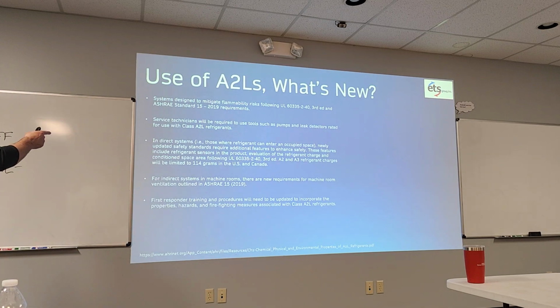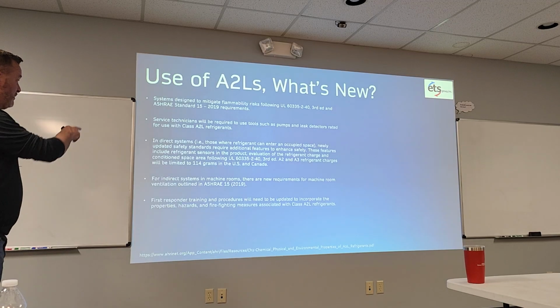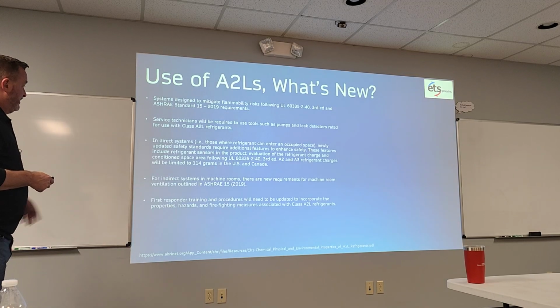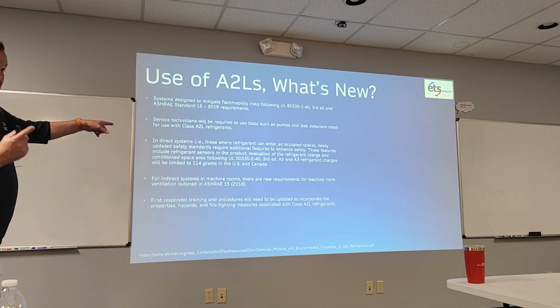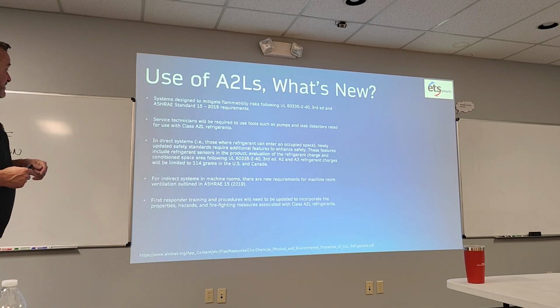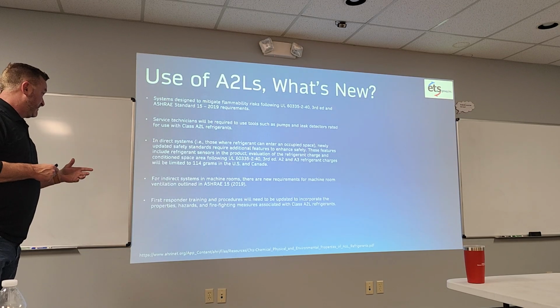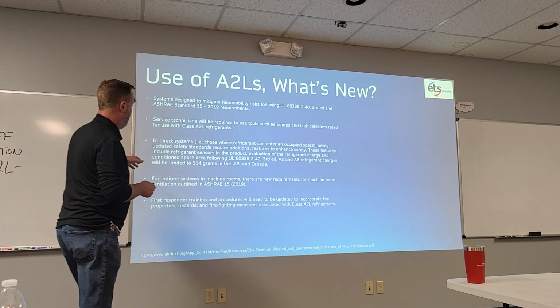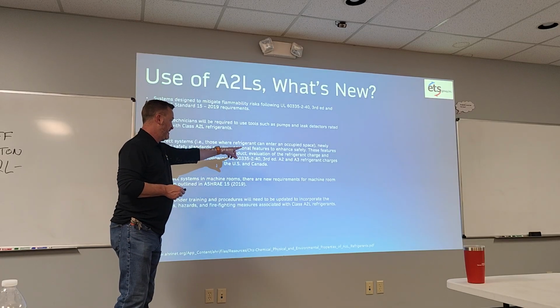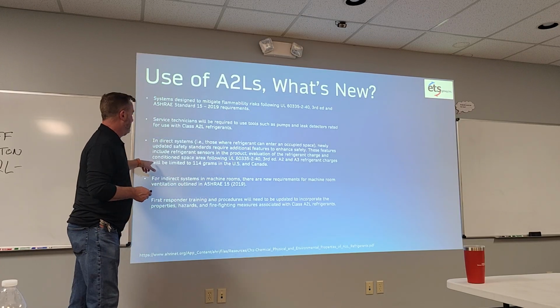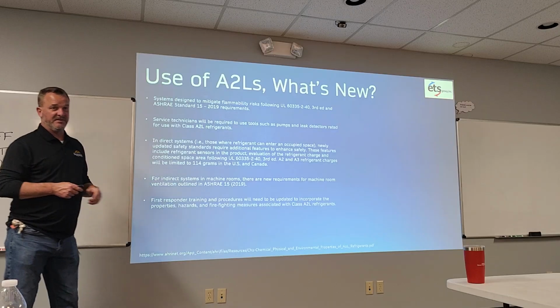Direct systems where refrigerant can enter an occupied space will have new safety standards, requiring additional features to enhance safety, like refrigerant sensors in the product and evaluation of the refrigerant charge in the conditioned space, following this UL code.